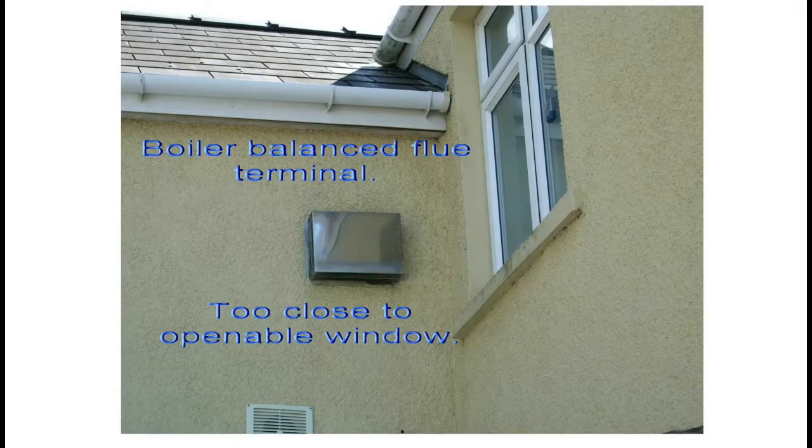Here's a real-life example of a balanced flue terminal which is too close to an openable window. This is a natural draft balanced flue. You can tell that because it's made of metal and it's a big square shiny terminal. In general, these are natural draft terminals.